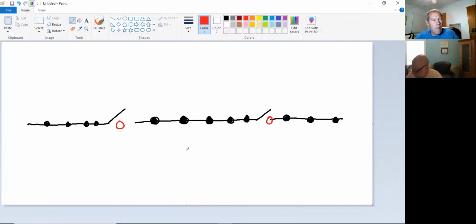So when a circuit breaker in a substation opens, can you see a visual open point? To a certain extent, you can. You see an air gap inside a metal box that's open, correct? Yes. All right. How about a circuit breaker in your house? When a circuit breaker trips in your house, can you see a visual open point? No. You cannot see in the wall. You cannot see air in between where it's energized.